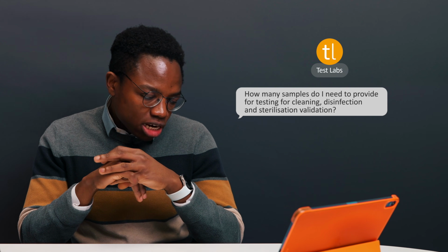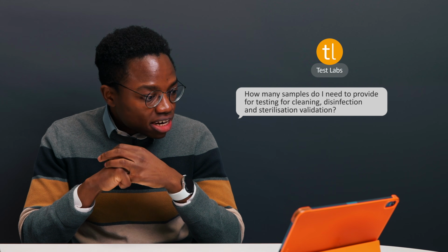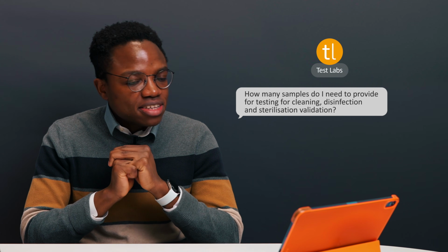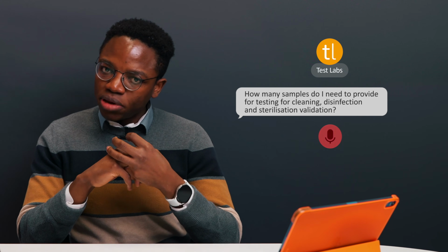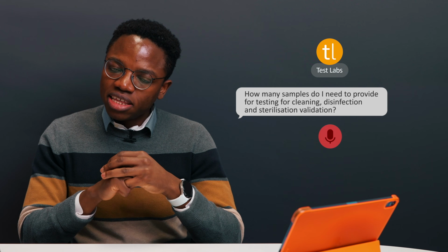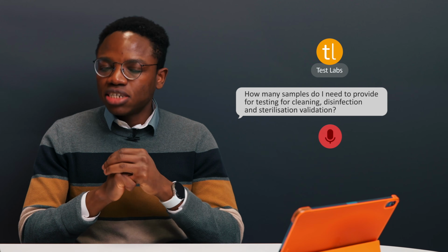And the next question is, how many samples do I need to provide for testing for cleaning validation, disinfection validation, and sterilization validation? So this depends on the lab and how robust they're being with the level of evidence they're generating for you. Us at Test Labs, for example, we would expect for cleaning validation at least 5 replicates of the worst case devices that you're sending to us. So for example, if you are sending us 6 different worst case devices, I would expect 5 of each of those devices to be sent to us.